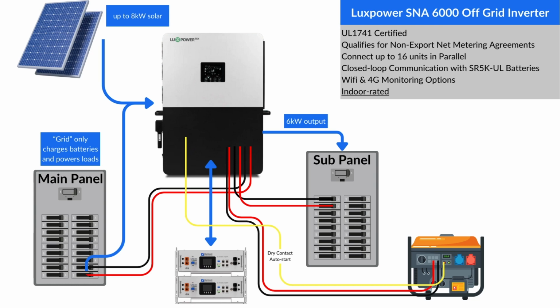It does have a grid input line, and grid energy only comes through the inverter to run loads or charge the batteries. There's no ability for this to export. It's not bidirectional. You can put up to 8K of DC coupled solar. There is a generator port. It does not have the ability to AC couple, but you can hook up a generator. It has dry contact auto start, and this has 6 kW of continuous output power.